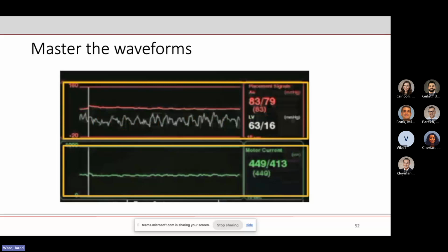Because your motor current is flat, I don't know what to make of that LV waveform, and your aortic pressure line is flat. And so this can mean two things. Before the Smart Assist Impellas came out, this used to just pop up as a big question mark on the Impella device itself. So this can either be a malpositioned Impella, in which case you just need to reposition it under ultrasound, or B, the patient has such low cardiac function that the native ventricle is unable to generate a pressure difference for the two separate sensors to monitor. So this could be either A, malpositioning, or B, really bad native cardiac output, in which case you can either A, put them on some drips, or B, just wait it out and hope for native heart recovery.